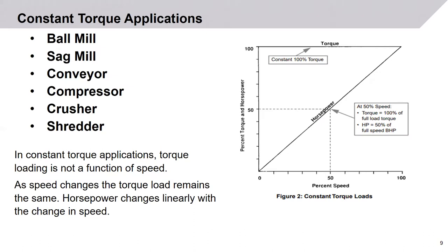Constant torque applications include ball mills, sag mills, conveyors, compressors, shredders, and crushers. In constant torque applications, torque is not a function of speed — as speed changes, the torque load remains the same. Horsepower changes linearly with change in speed.